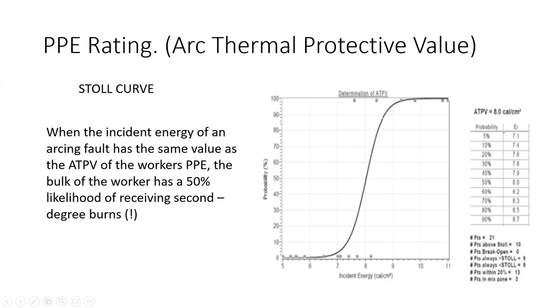But don't despair, because if we have a look, if the incident energy can be backed off a little bit to say 7 cals, you can see now we've got a 95% probability of being protected. There's only a 5% probability of breakthrough. So there's a clear message from that, and that is to select the next highest rated suit for your calculated incident energy.